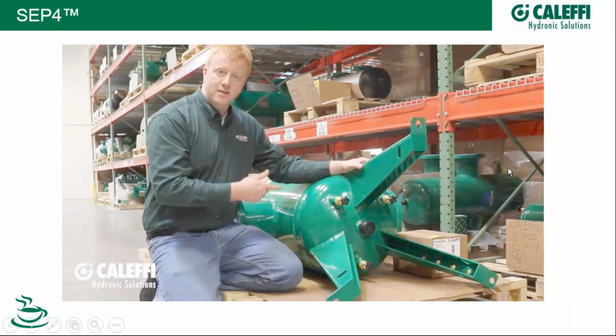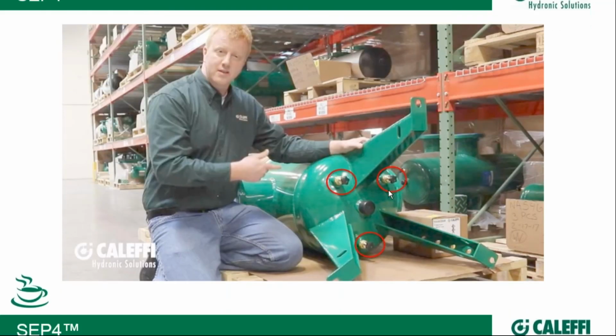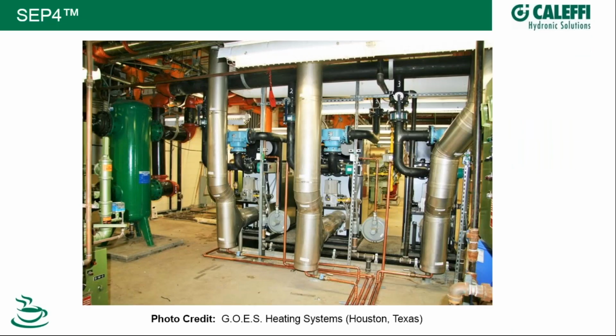Now, getting back to this photo, you can see in the background a bunch of our separators over here, but if you squint your eyes, you can see a smaller separator, a combination air and dirt magnetic separator, and it only has 1 magnet. I think 6 inches is our cutover point where we go from 1 magnet, and from 6 inches up, we go to 3 magnets to get that power I mentioned that's required to do a good job. I think we're doing good on time, and we're going to have some time left for questions.